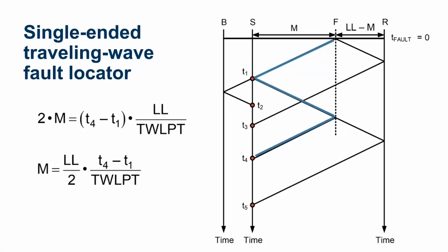So one thing to notice here is that we've got some other arrival times. We've got T2. This is an arrival time that is before T4. This is a reflection from the remote bus. We've got the traveling wave launched from the fault point, hit our station S, hit this terminal, some passed through to the remote bus, and now some of that wave that hits the remote bus is going to reflect back. So we're going to see that here at S.